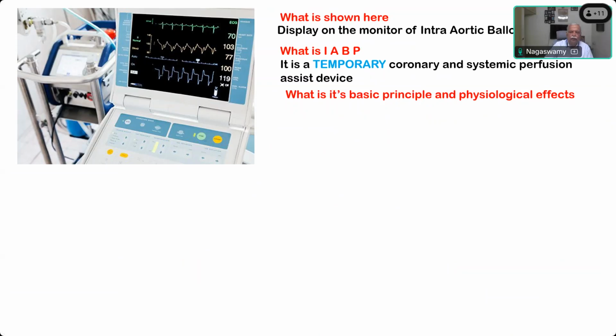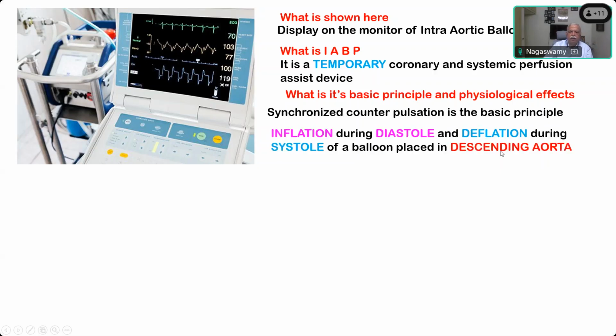Helium is used to inflate the balloon during diastole, so as to increase the coronary perfusion, and it deflates during systole. The basic principle is synchronized counterpulsation.